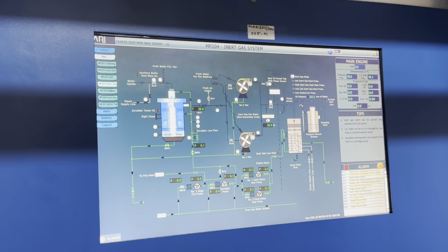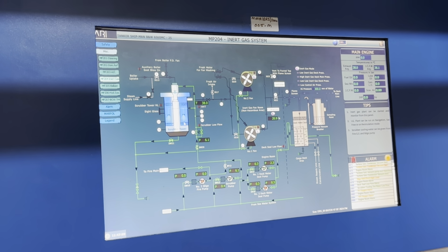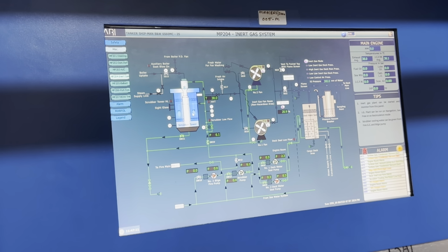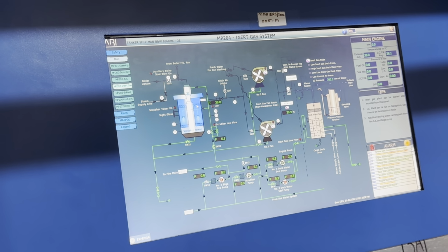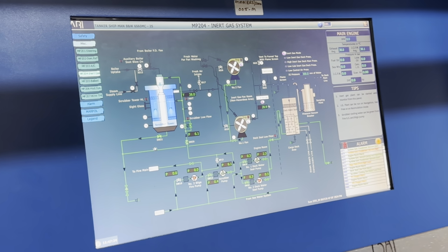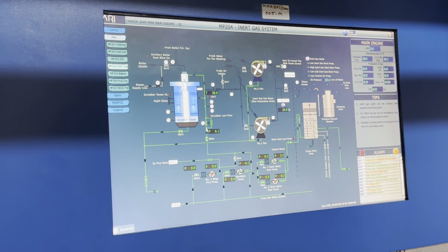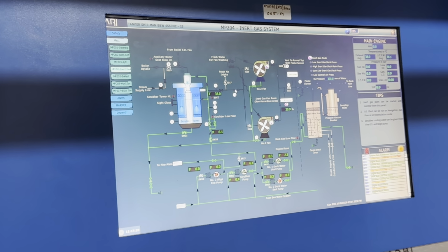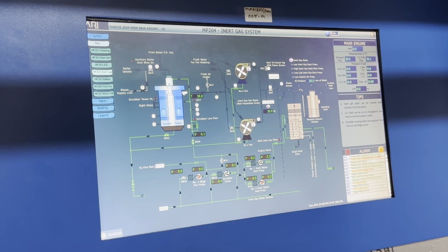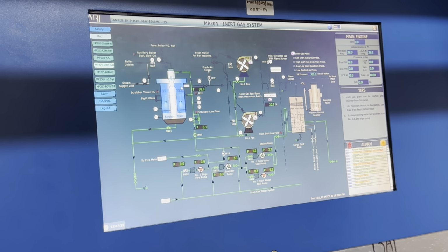After passing through and getting clean here, the IG passes through the demister. The demister removes the water particles, which become larger drops, and then the drain, and this soot water is discharged to sea. Now after the demister, the IG comes here, correct?